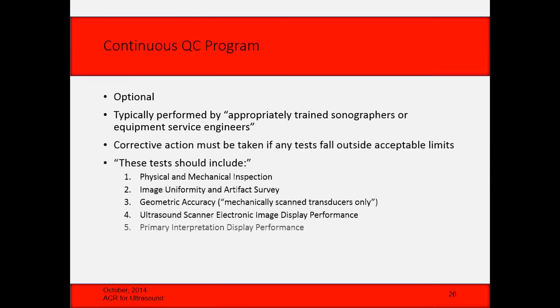However, as I mentioned earlier, if you've had a software upgrade lately, I would check it at least once to make sure all the probes are still measuring correctly. The ultrasound scanner electronic image display needs to be checked, and then if that's not used for making diagnoses, the workstation display needs to be checked. Preventative maintenance must be scheduled, performed, and documented on a regular basis. And service must be done to correct any deficiencies found, and those need to be documented and those records maintained.